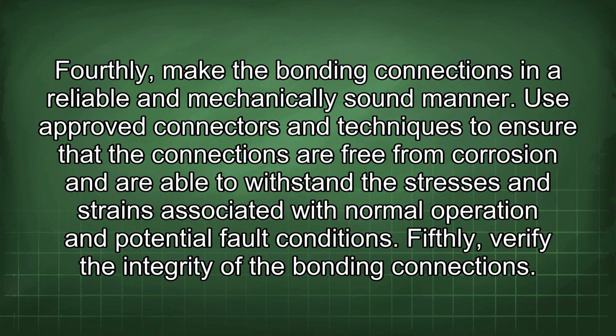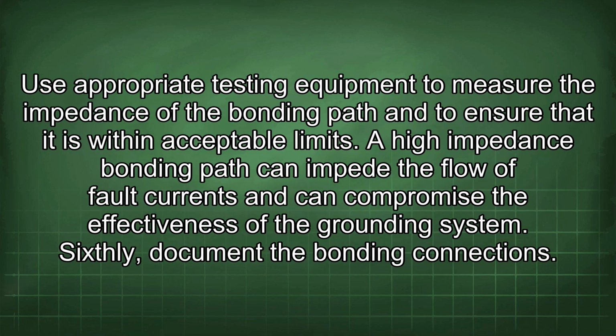Fourthly, make the bonding connections in a reliable and mechanically sound manner. Use approved connectors and techniques to ensure that the connections are free from corrosion and are able to withstand the stresses and strains associated with normal operation and potential fault conditions. Fifthly, verify the integrity of the bonding connections. Use appropriate testing equipment to measure the impedance of the bonding path and to ensure that it is within acceptable limits. A high impedance bonding path can impede the flow of fault currents and can compromise the effectiveness of the grounding system.